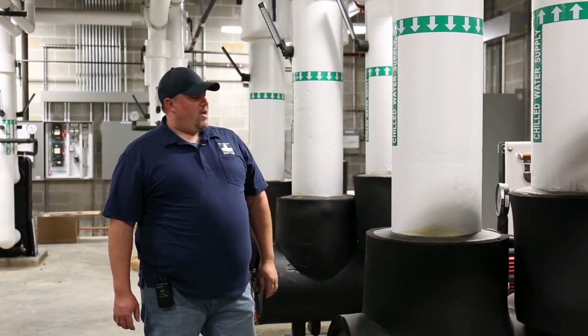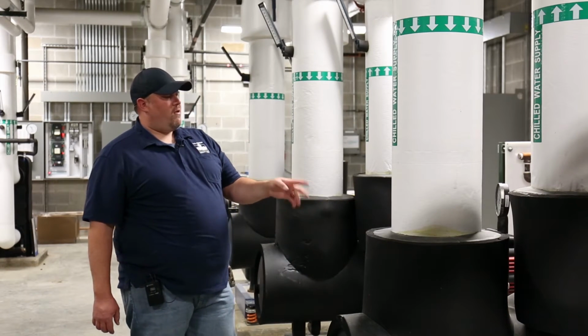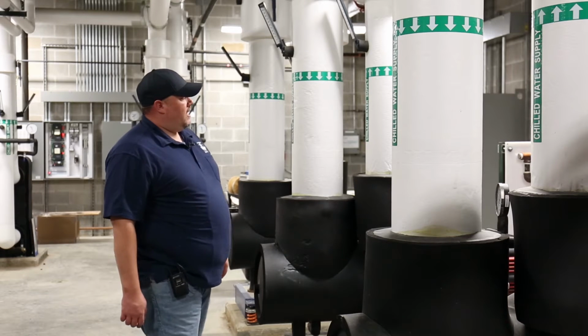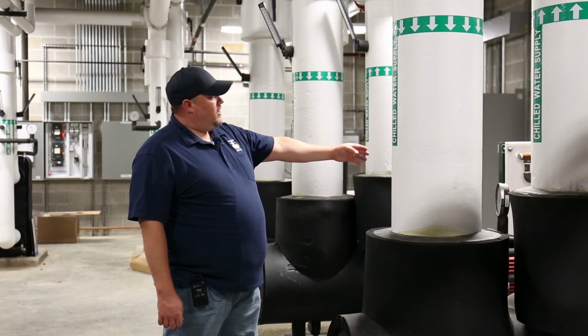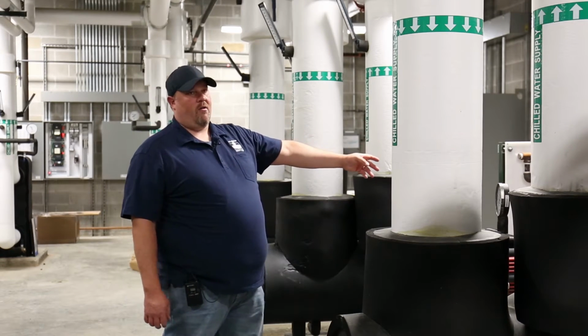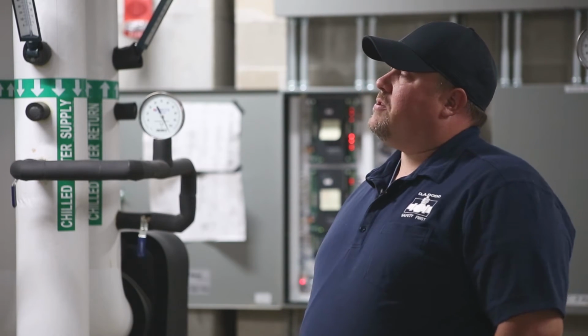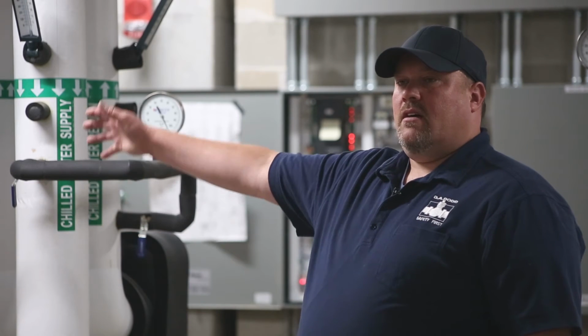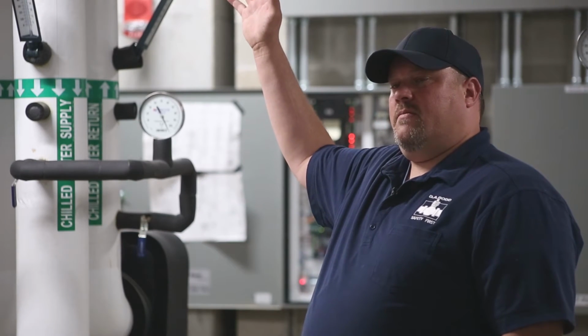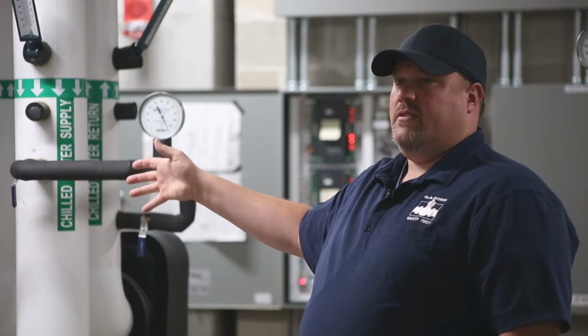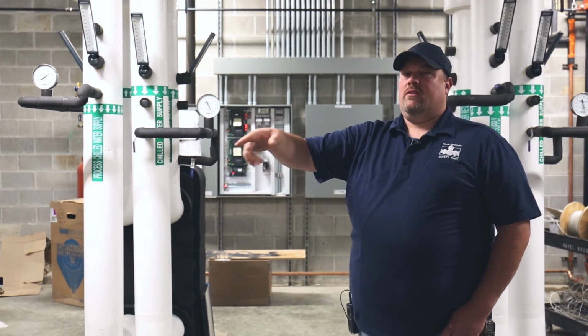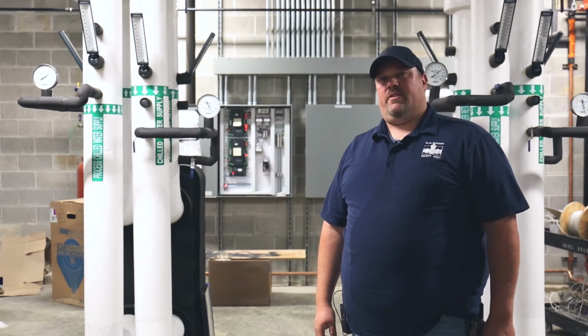As well as with the pumps, we have a pressure differential for each one of them, including a chemical feeder in the rear and a chemical test coupon rack. From this point, from the pumps, the chilled water supply goes out to the building, up to the penthouse to feed the 6 air handler units, and then returns back down and exits out to the campus.